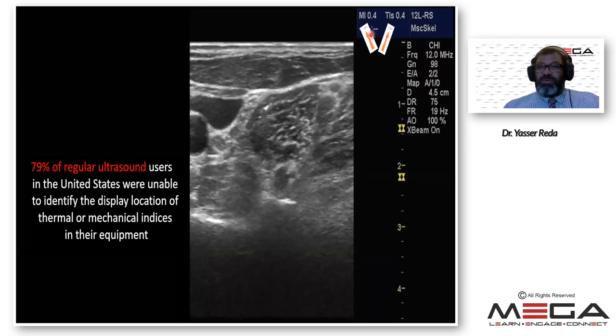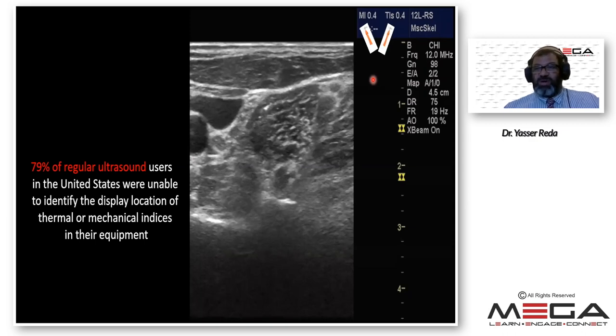On all machines you'll find MI and TIS, called mechanical index and thermal index. This is very important. If you do an ultrasound and it increases double from the baseline, take care - you must use more gel, you must move your probe.